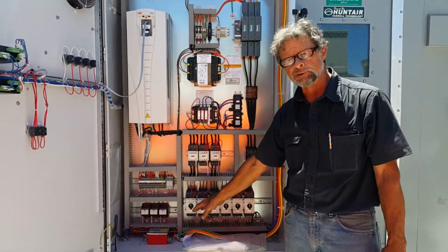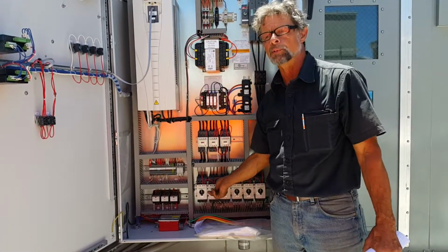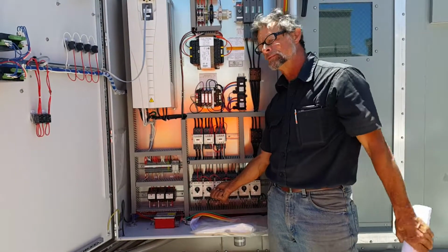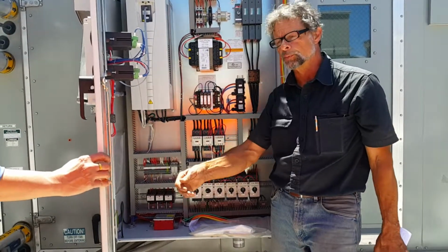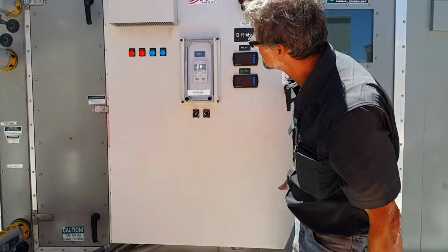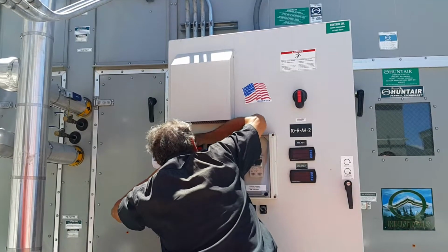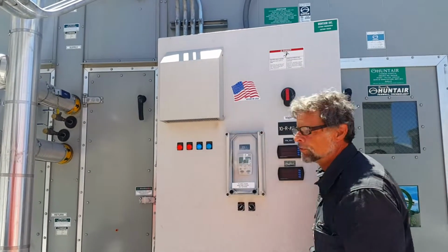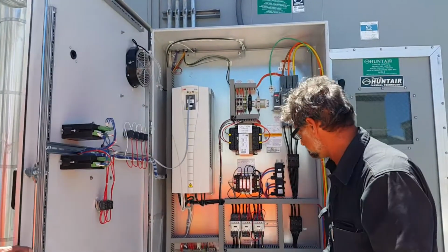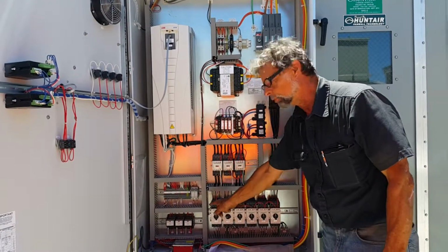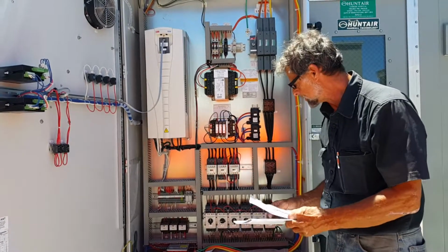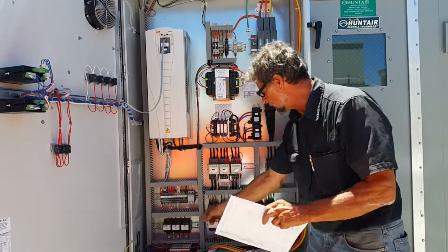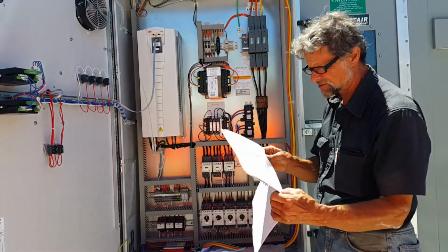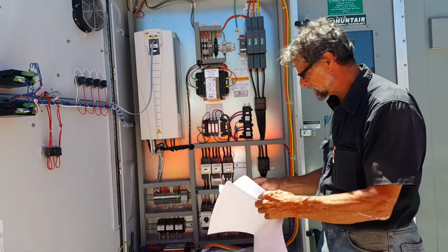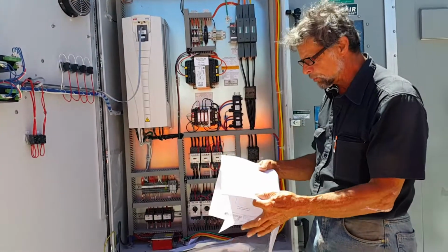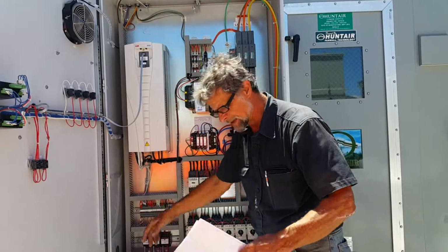In a lot of cases, when we have multiple motors like this, we just trip one motor. You walk in, you'll see that light on. It says you got a motor out, and your circuit breaker will be in trip position. External fault light is supposed to be on. There may be a problem with the light. That light is in series with all these connections. I'll double check that wiring diagram. Usually you've got a fault, external fault, some sort of fault would be on there. Sometimes, depending on how they wire it up, it may just be wired to a set of contacts here.